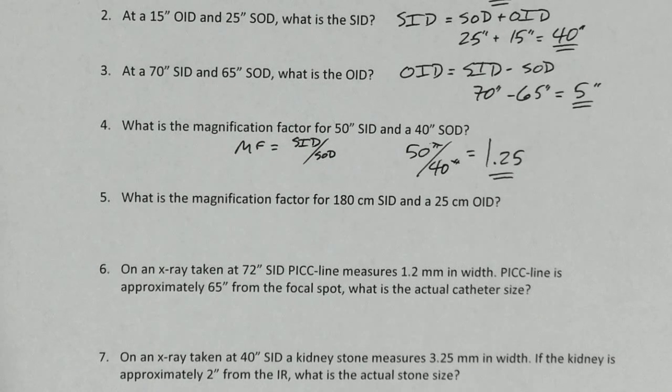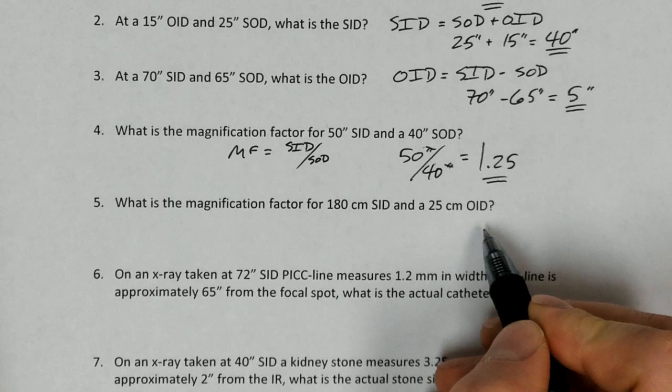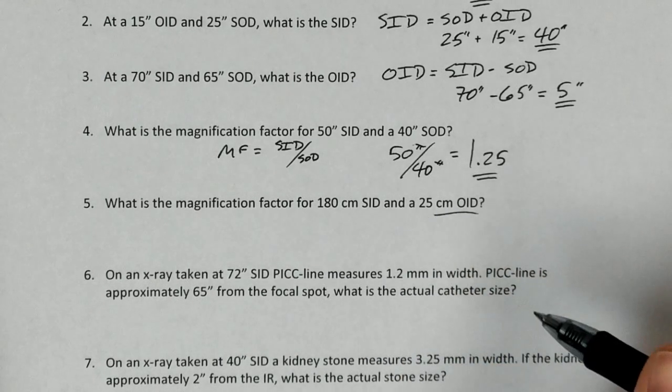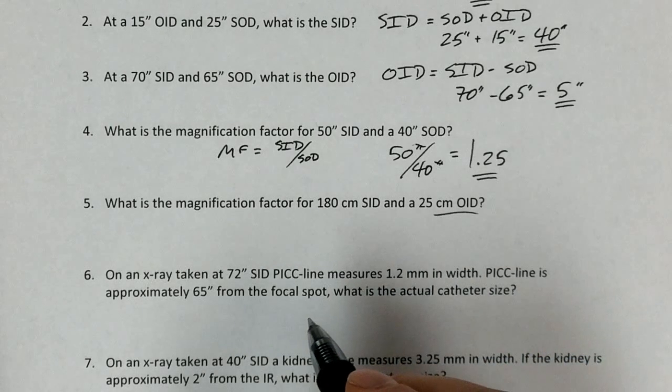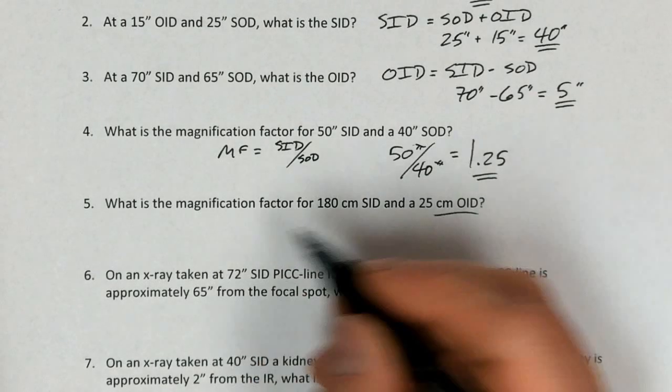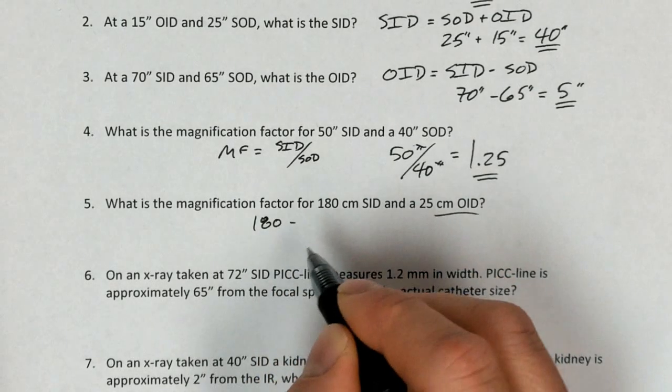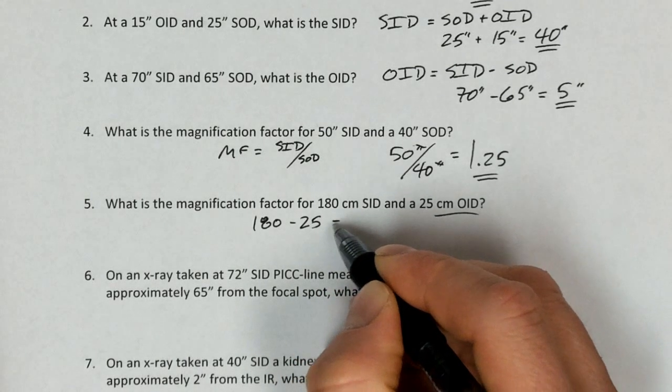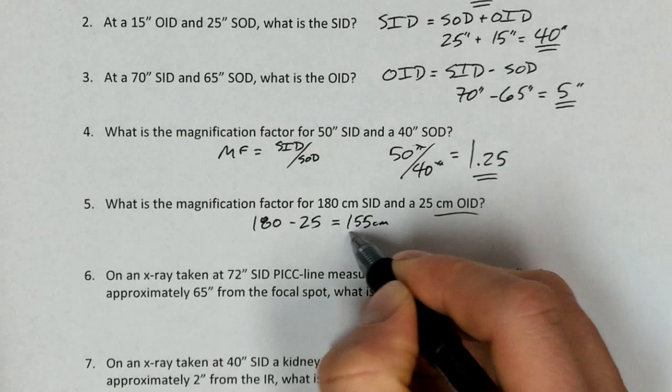So what is the magnification factor for a 180-centimeter SID and a 25-centimeter OID? Now, they didn't give us what we actually needed to solve this problem. We're going to need to calculate the SOD based on the OID that we've been given. And so we've got to do a couple of different steps here. First, we're going to calculate what the SOD is. And so we take that SID of 180 centimeters, subtract out that OID of 25 centimeters, and that's going to give us 155 centimeters. That's the SOD.